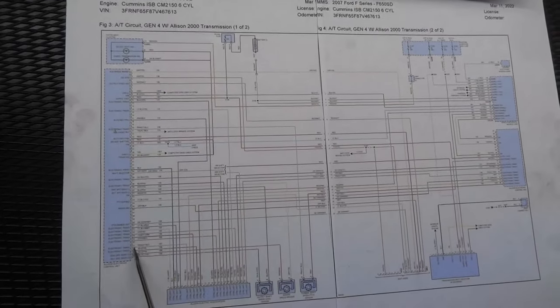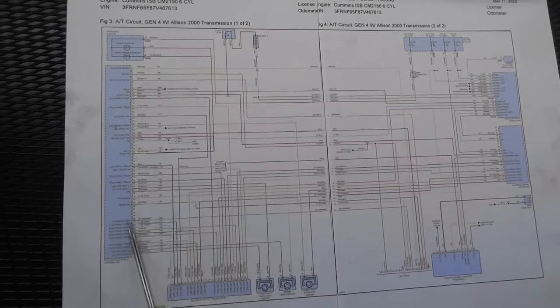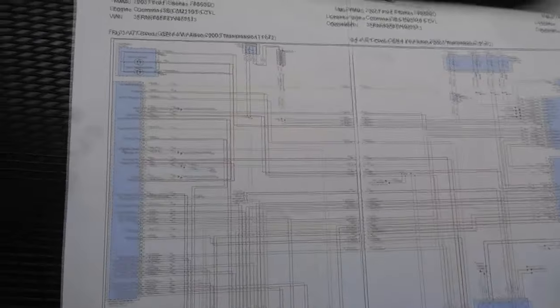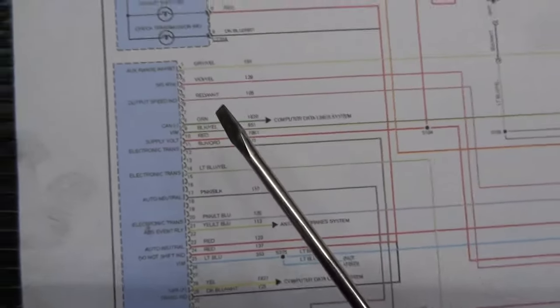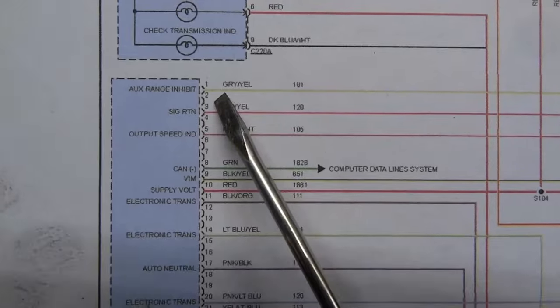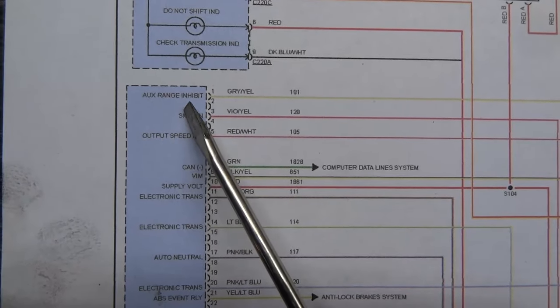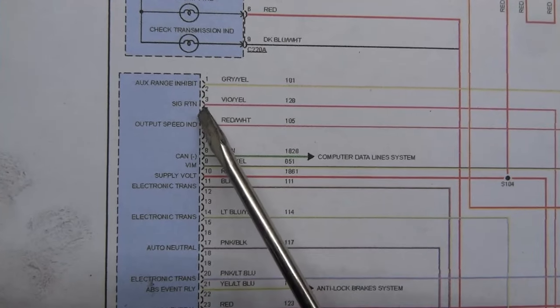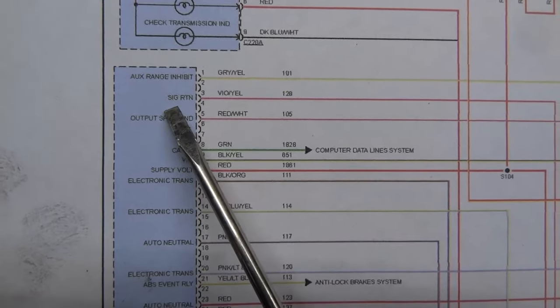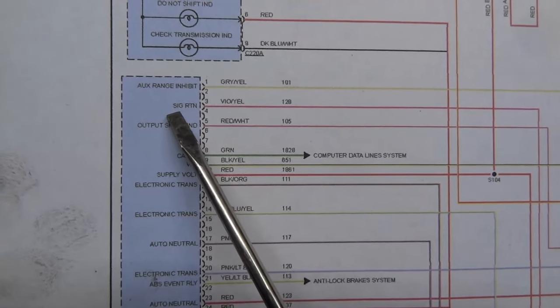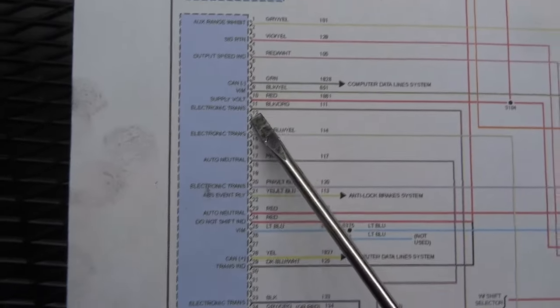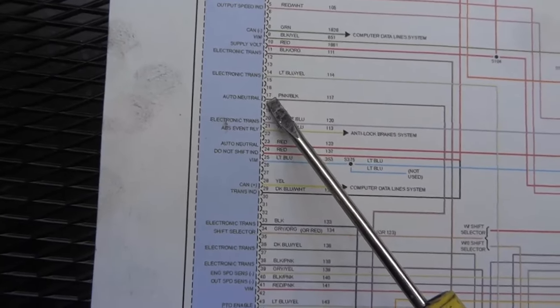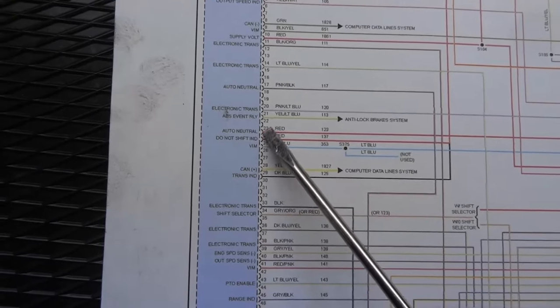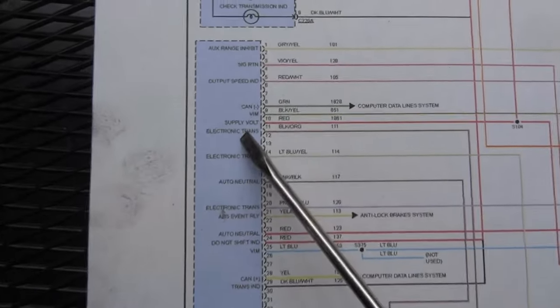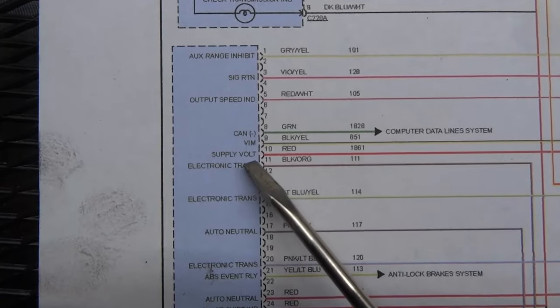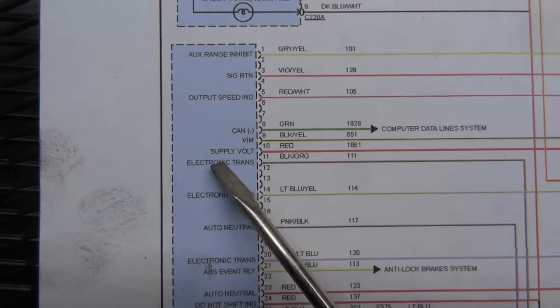So what I'm looking for is power wires and ground wires. We're gonna start up here. Pin one says auxiliary range inhibit, and pin three is sensor return, which looks like a sensor ground. Now we're gonna keep going down the line until we see a wire that says system voltage or supply voltage. It looks like I see one that says supply voltage at pin 10, a red wire.